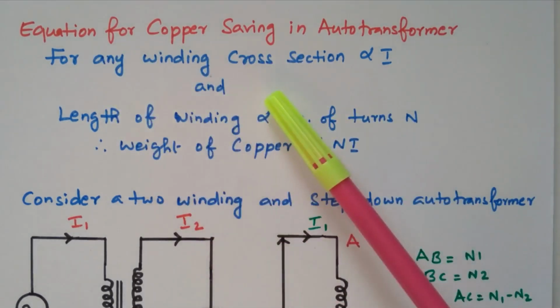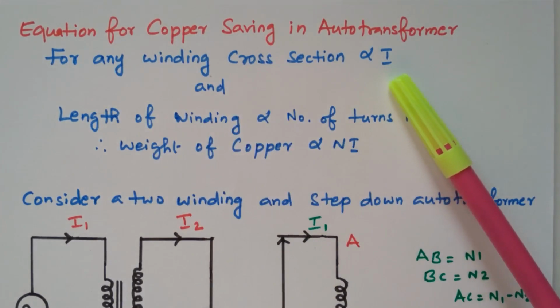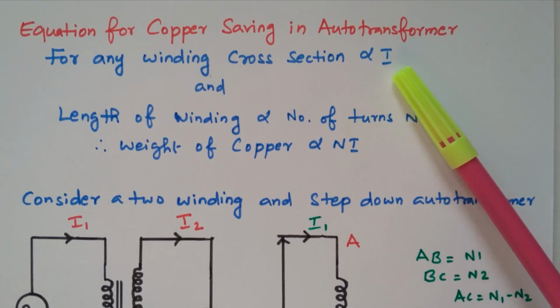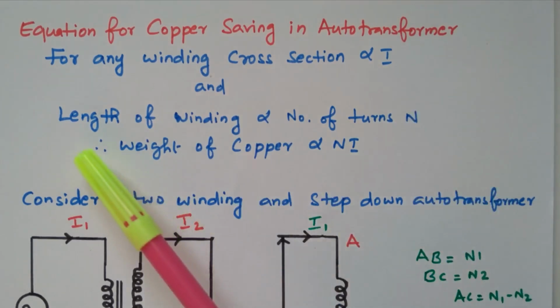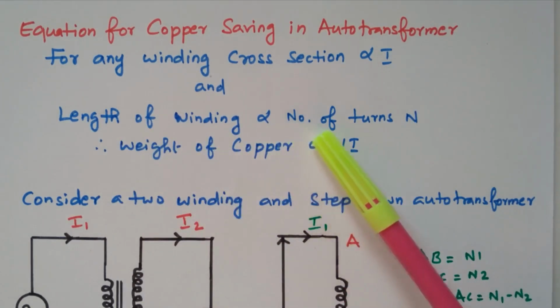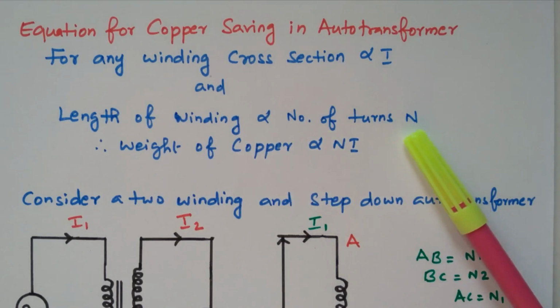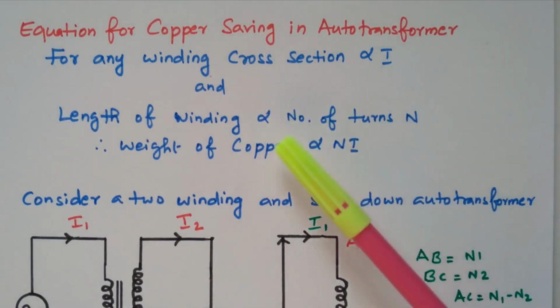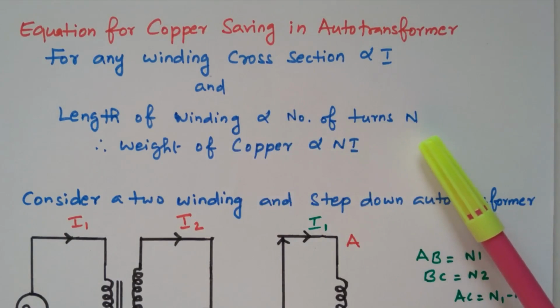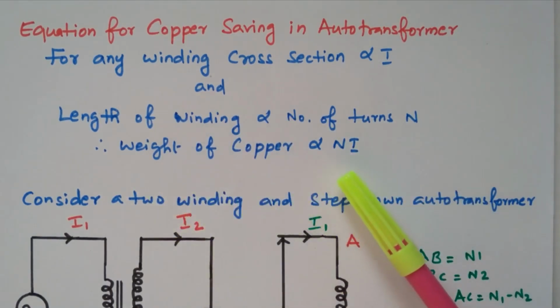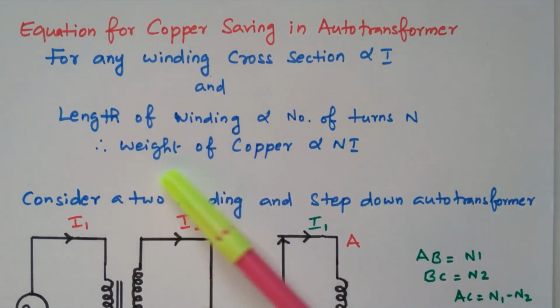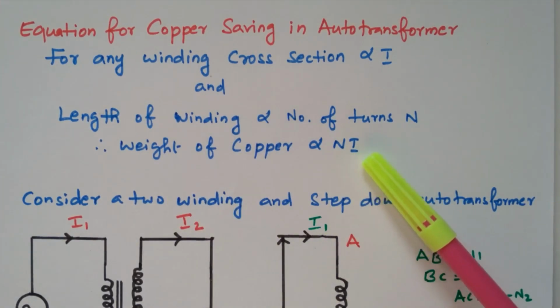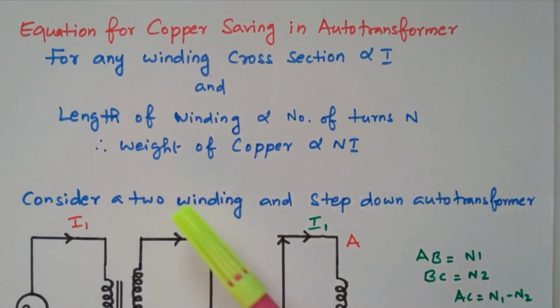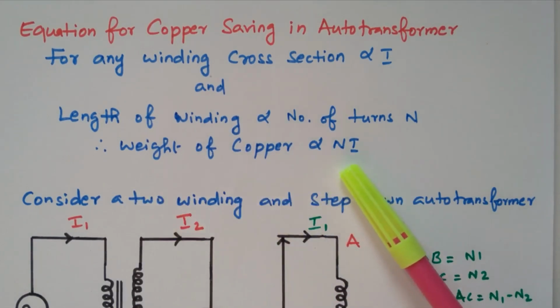For any winding, the cross section is directly proportional to current. The cross sectional area, or the size of the cable, is decided by the current I. Similarly, the length of winding is directly proportional to the number of turns N. So the current decides the size of the wire, and the length of the wire is decided by the number of turns. Totally, the weight of copper is directly proportional to N into I. These are the two primary factors deciding the weight of copper: I refers to the area, N refers to the length.